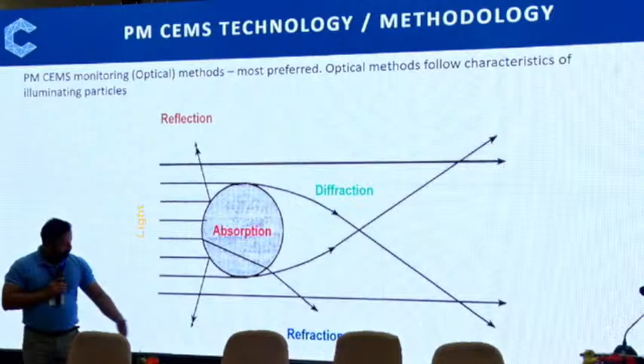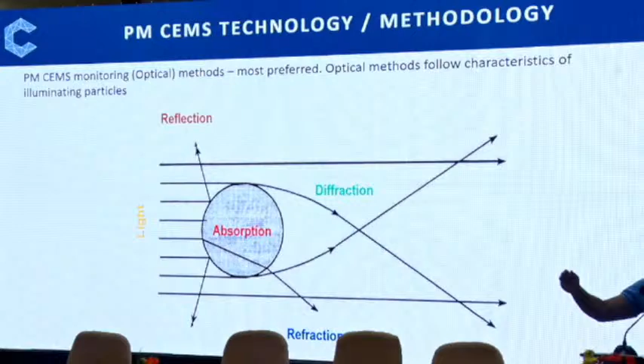When you have a lower concentration, 30 milligram, 20 milligram, what is the base for? Forward scatter, because it can monitor to that limit. In between, you can use the backward scatter. So this is the overall fundamentals of PM monitors. There are other variations, such as the diameter of the duct; if it is higher, you can go a little lower. We'll get into more detail.